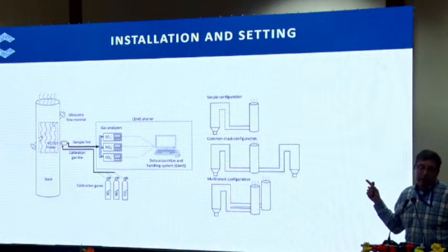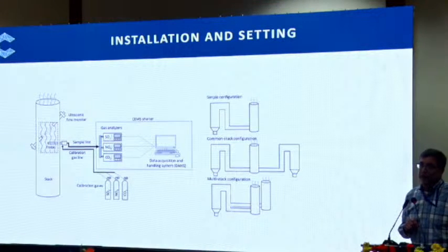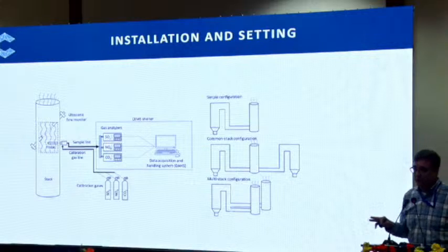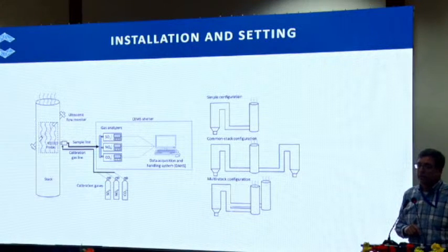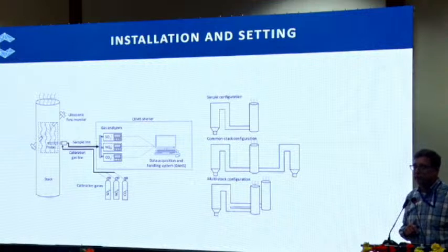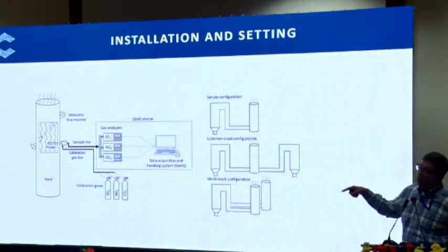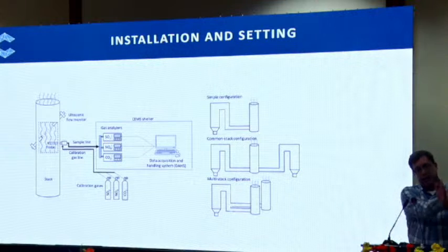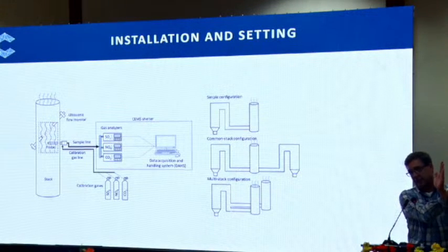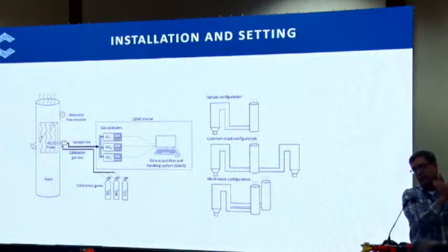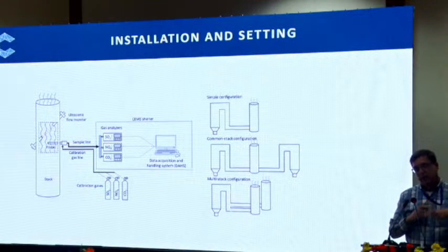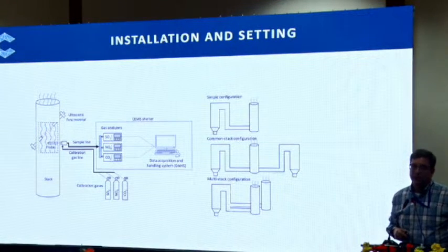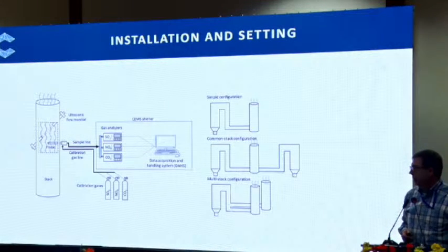In areas where you could have very turbulent flow, such as after FGD, once you install multi-vessel FGDs, for example, you can get some very interesting flow configurations as you shift between vessels. To help accommodate that, reduce the amount of cyclonic or turbulent flow measurement, and improve the accuracy, we typically use 2 ultrasonic flow systems in a pattern we call a lazy X system. It's not perfectly perpendicular, but it's off. And what that allows you to do is measure in 2 different directions and help minimize turbulent or cyclonic error that you may encounter.